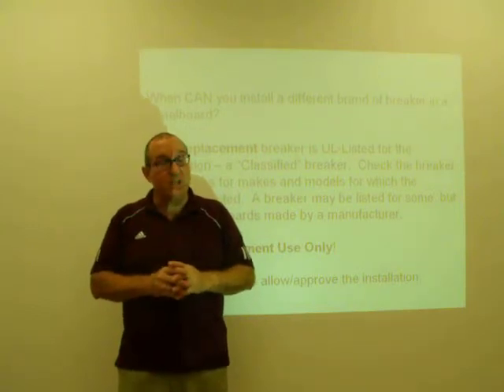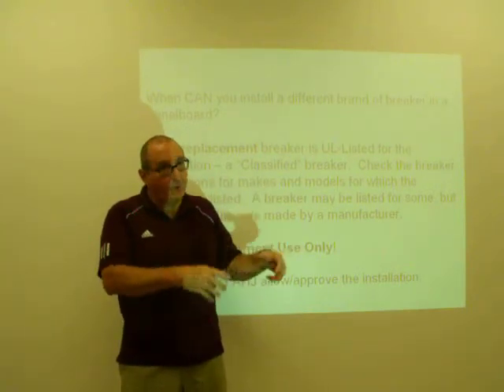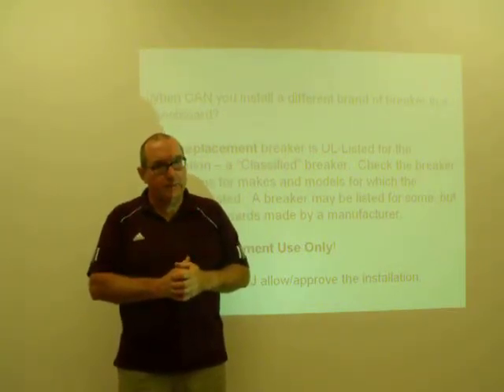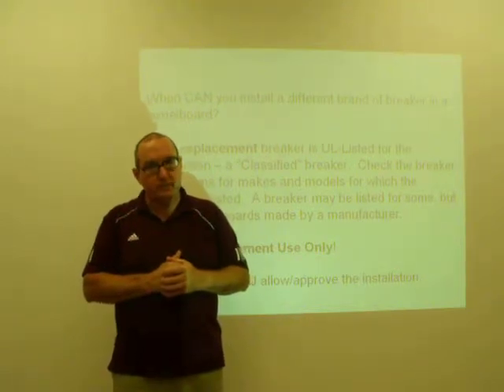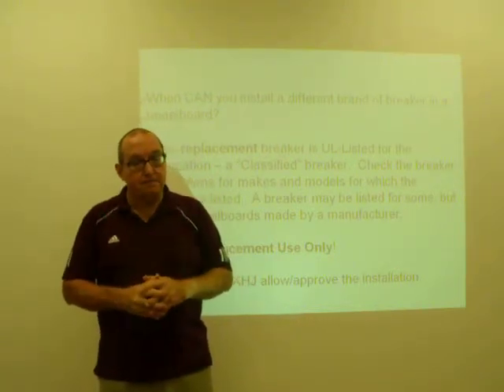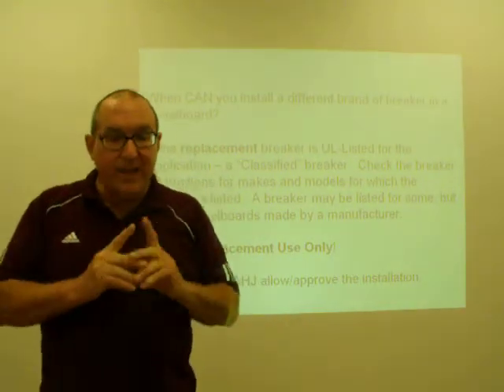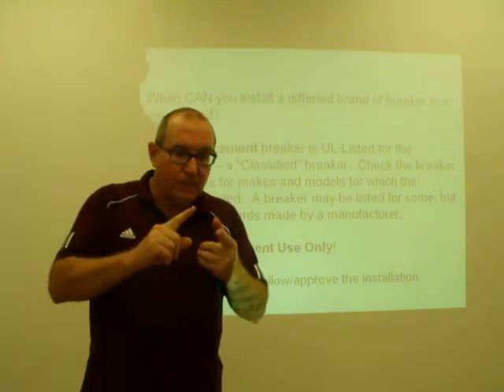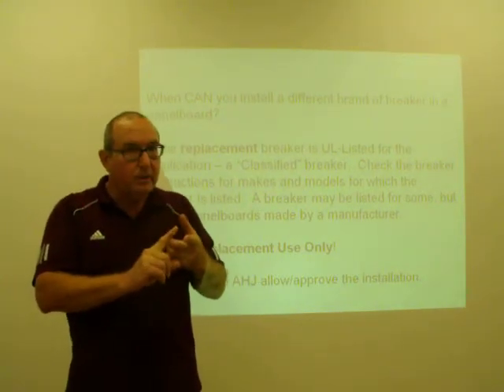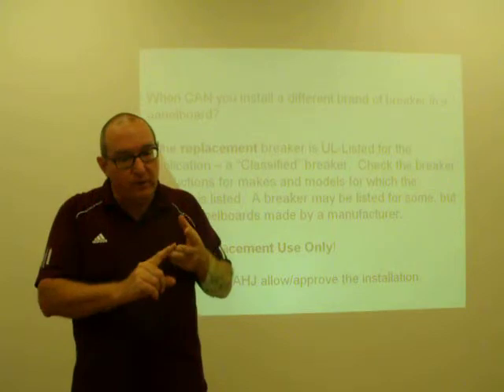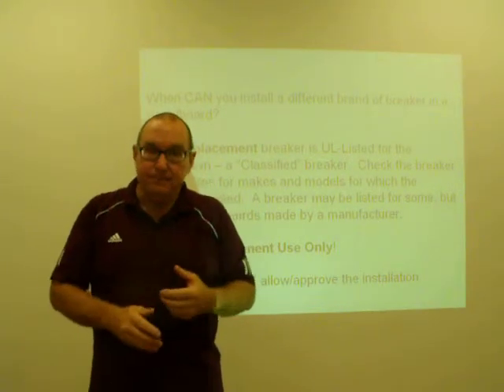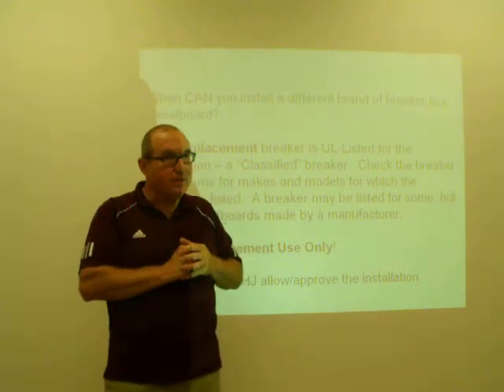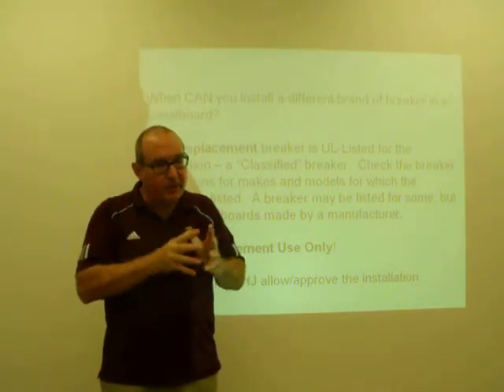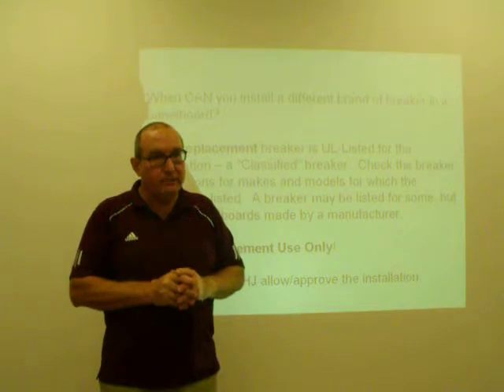And I haven't known an inspector that would pass one, and depending on how you want to read the code, it's not authorized. The concept there is if you buy the panel board, buy the breakers to go with it at the same time that you're at the supply house, so you don't have to come up with some sort of solution to save yourself some time and money because you made a mistake. So, the second factor would be, we already said, is the breaker listed for that purpose, that application, and will the authority having jurisdiction allow or approve the installation? Just because the breaker is UL listed and it fits does not necessarily mean that the AHJ that you're having to deal with is willing to approve that installation.